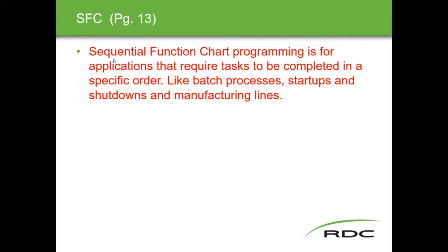Okay, so here, big red letters: sequential function chart programming is for applications that require tasks to be completed in a specific order, like batch processes, startups, shutdowns, and manufacturing lines. As you read through the section in the ILM, you'll see that most of the processes it's giving you programs for are either a batch type program or something that comes on and off once in a while. Not PID control, not complex math, not things where other languages are more proficient. So this is the main purpose for SFC: sequential activities that get performed in steps one after the other.